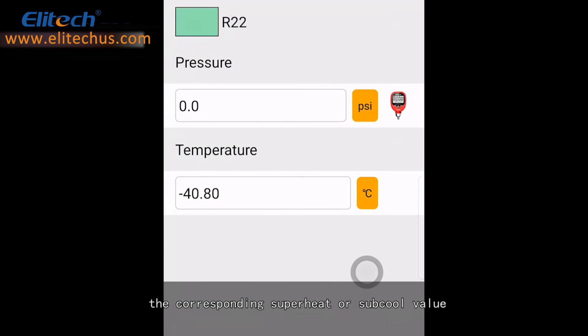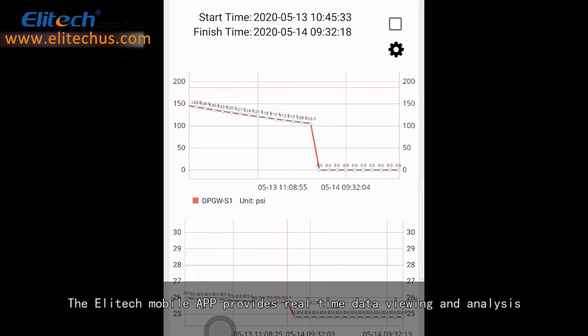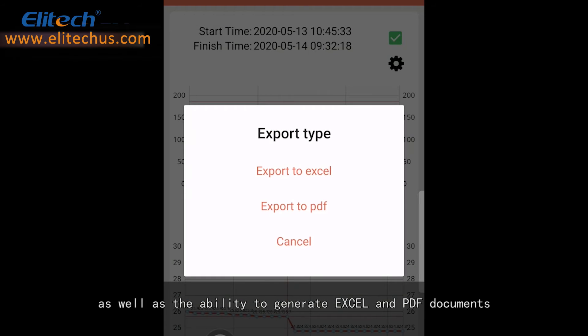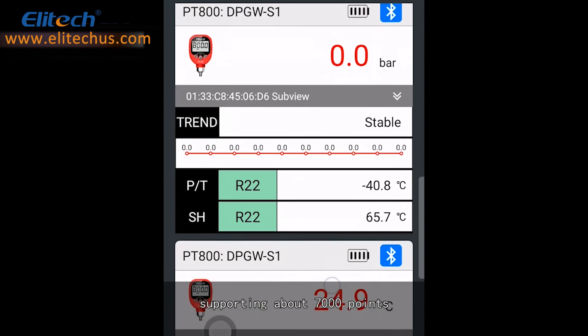We support 140 kinds of refrigerant saturation temperature data view. SC-SH will display the corresponding superheat or subcool value. The Elitech mobile app provides real-time data viewing and analysis, as well as the ability to generate Excel and PDF documents. The product supports the recording function, supporting about 7,000 points.